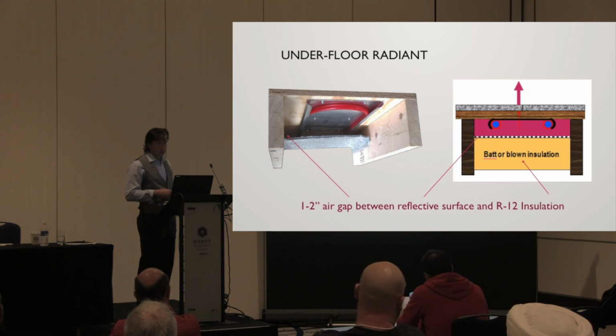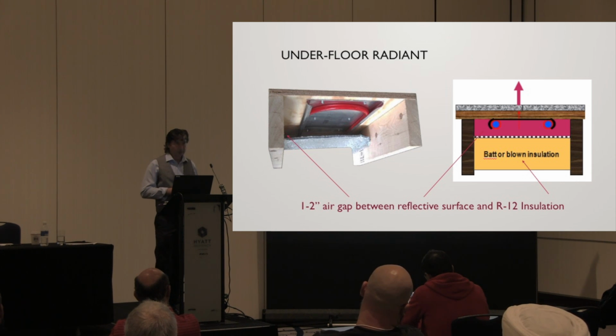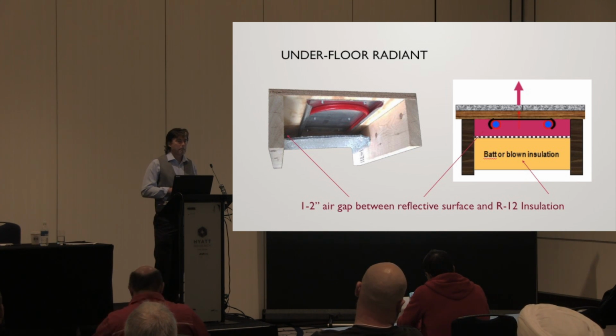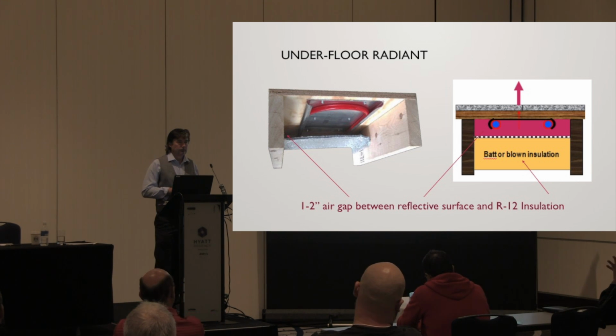Now, Scott, the one on the left is a real sleeper, extremely powerful for two reasons. The aluminum plate, what you call the heat transfer plate, does the obvious of distributing the heat over a greater area underneath that subfloor. But what most of our industry doesn't recognize, it serves additional benefit. When aluminum is a reflective surface on its own and is hot, it cannot radiate. So the mere act of putting the aluminum and attaching it to the plywood means that in that area which the aluminum is covered, it radiates almost no heat down. So a far higher percentage of your heat's going up than you would have thought at first guess.